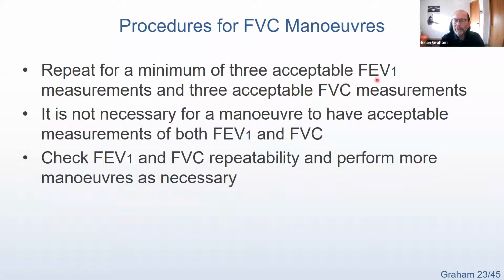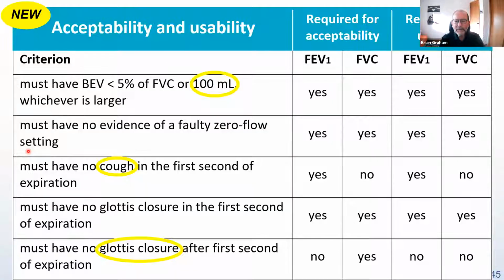So just as in the previous ones, we repeat for a minimum of 3 acceptable FEV1 measurements and 3 acceptable FVC measurements. Now the nuance, the difference here is that in the old guidelines, it said 3 acceptable blows or tests. What we've done is to separate that. You don't need to have tests that have both FEV1 and FVC acceptable measurements. You just have to make sure you've got 3 acceptable of each in that case. And so the other thing now that once you have 3 acceptable of each FEV1 and FVC, then you check to see if the repeatability is met, and do more if you need.